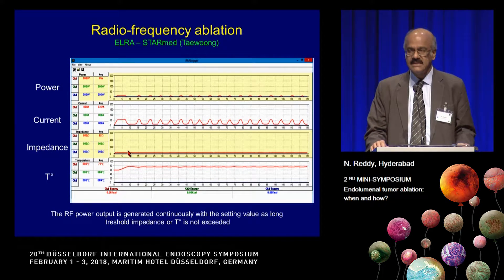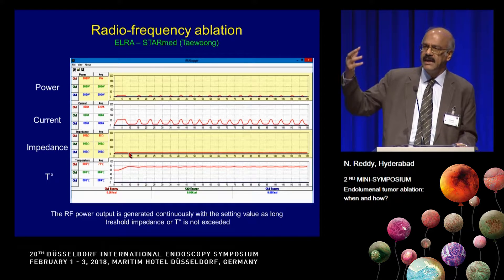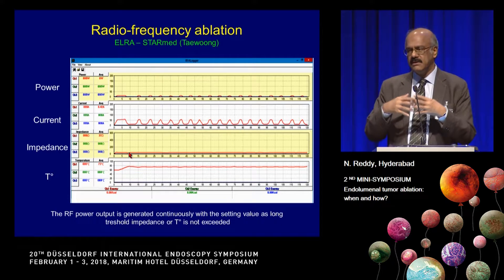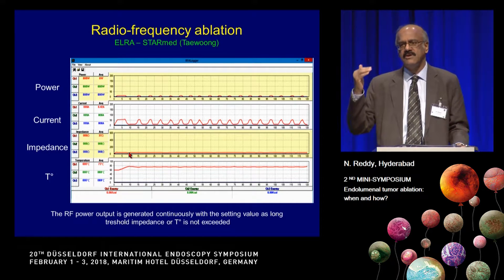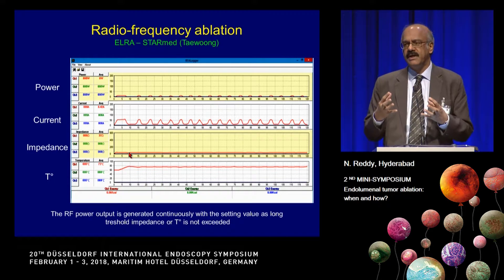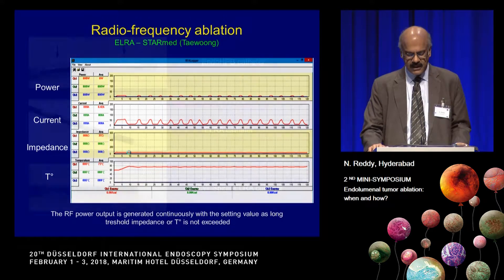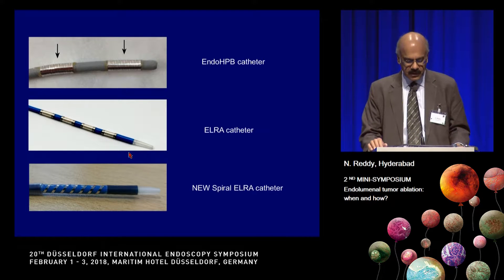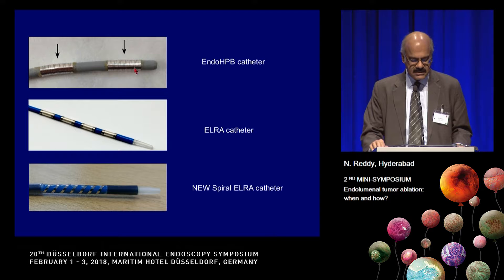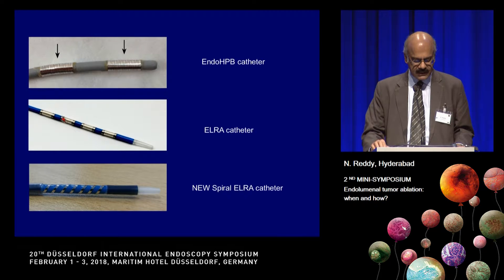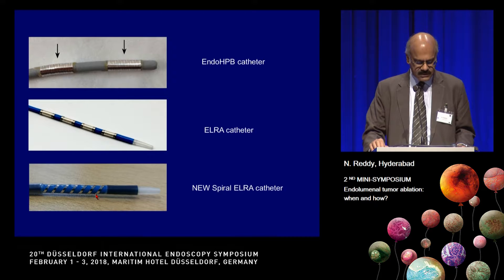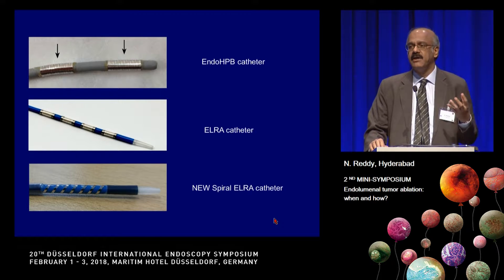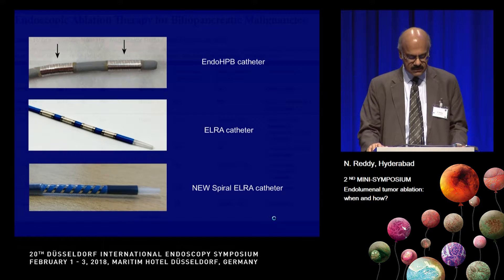The other important parameter is impedance, which we keep measuring constantly — if impedance goes high, the tissue is completely burnt and RFA efficacy falls. We need to maintain low impedance, a temperature of 75 to 80 degrees, and a two-minute period to produce effective RFA. There are now three catheter types: the standard Habib catheter, the newer ELRA catheter, and the spiral catheter. Experimental evidence suggests that spiral electrodes give much better ablation than standard round electrodes.